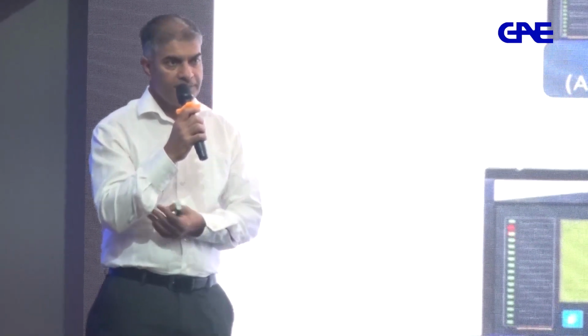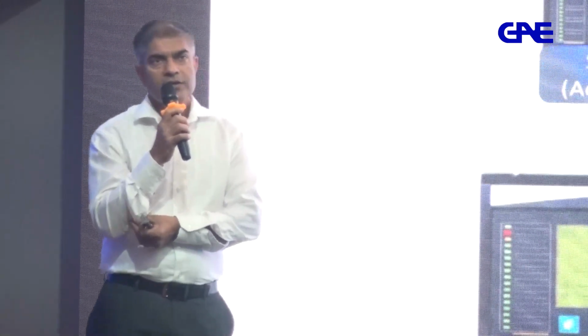In PLN, I don't know how it is done. In many other substations, power quality is still with conventional wiring, because there is no method for merging unit. Normally they work on 80 samples per cycle, right? And with 80 samples per cycle, you can monitor up to 10th or 15th harmonic. Now the power quality standards, you need to monitor up to 50th harmonic.